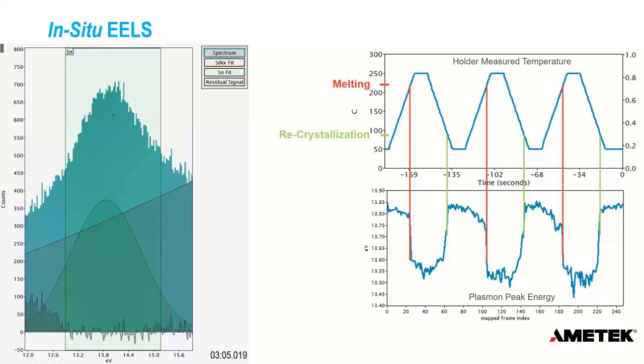In this case, this was a DENSsolutions heating holder, but this would also work with one of our GATAN heating or cooling holders. Anytime that we're controlling the temperature, we are generating a plot like this whenever I collect my EELS data or TEM video, making it really easy to go back and correlate the two. I can look at the points where the plasmon peak energy drops dramatically and see that this is actually the exact same temperature in each of these cycles — that's the melting temperature of this tin nanoparticle. Then it recrystallizes at a much lower but quite consistent temperature. This entire analysis probably took me five to ten minutes after the data was collected.